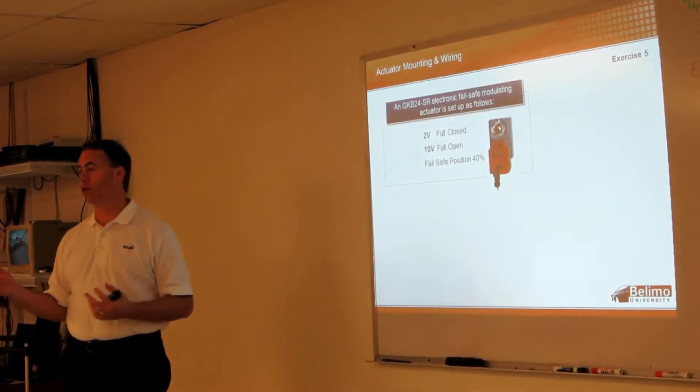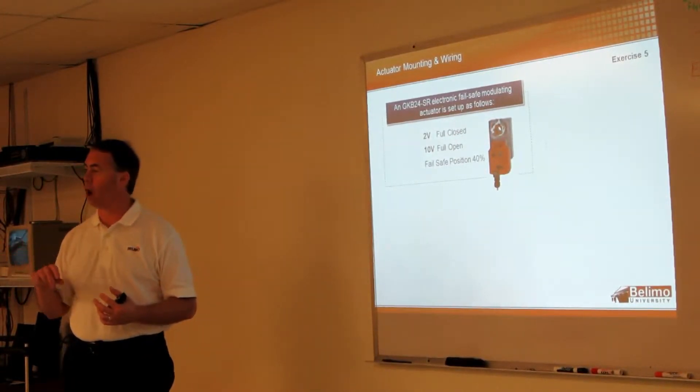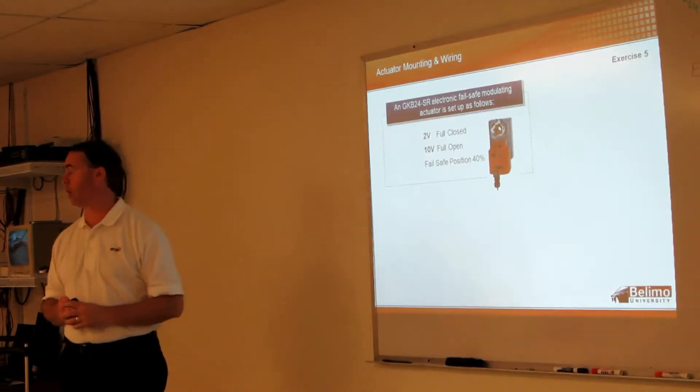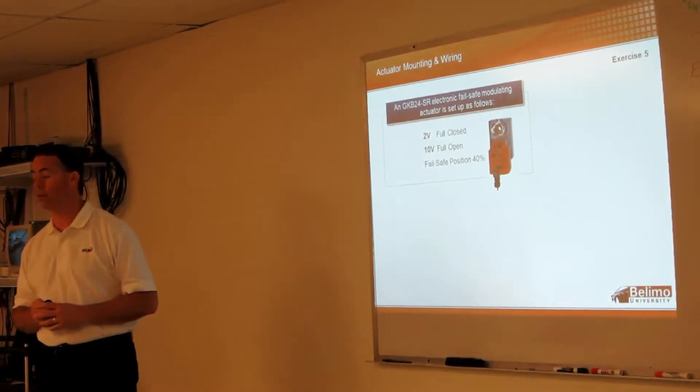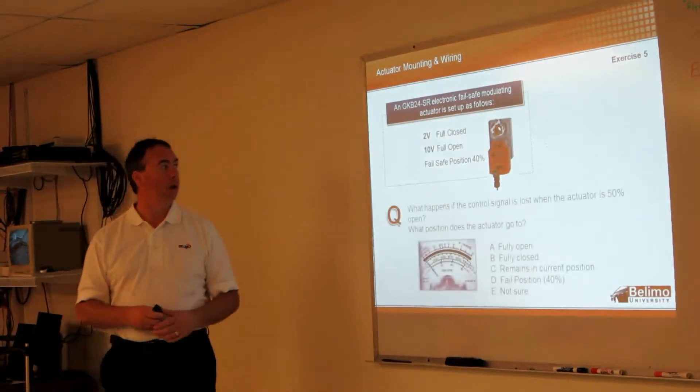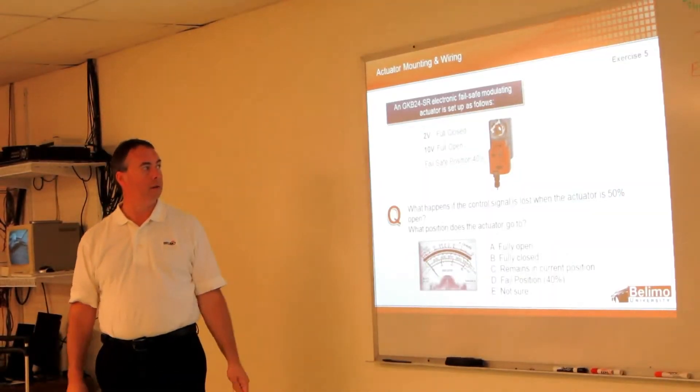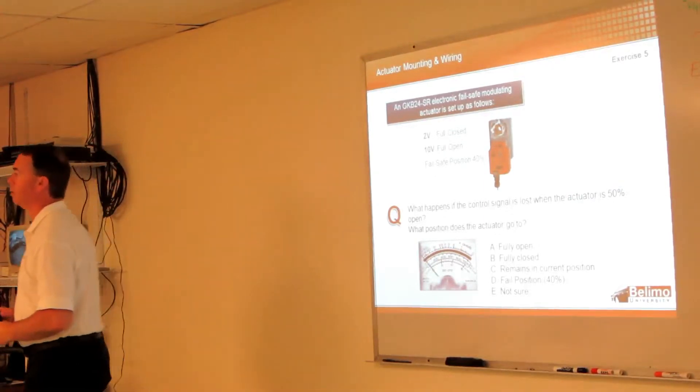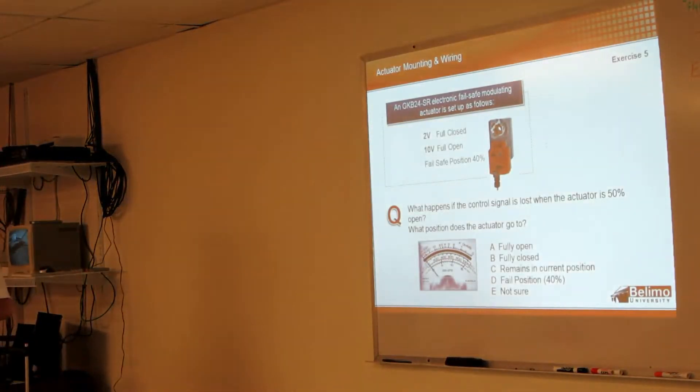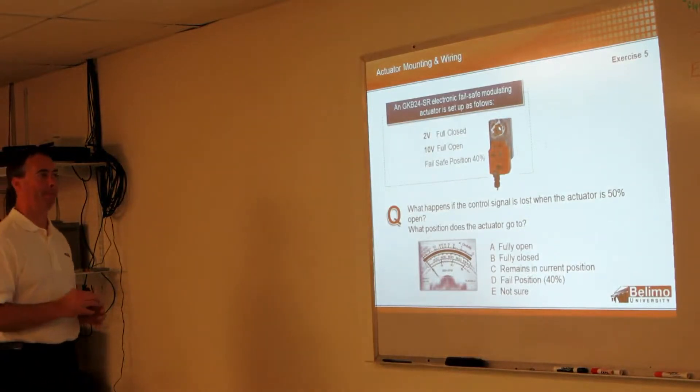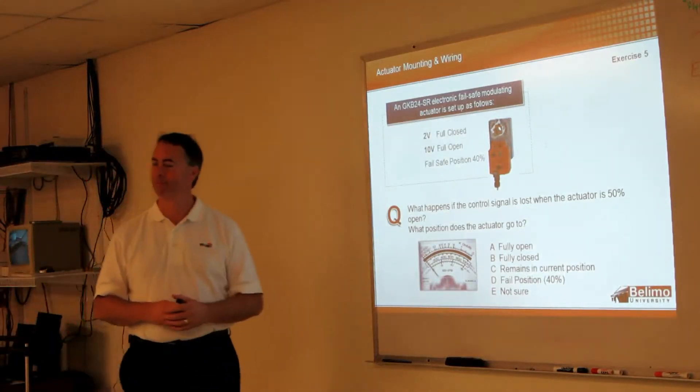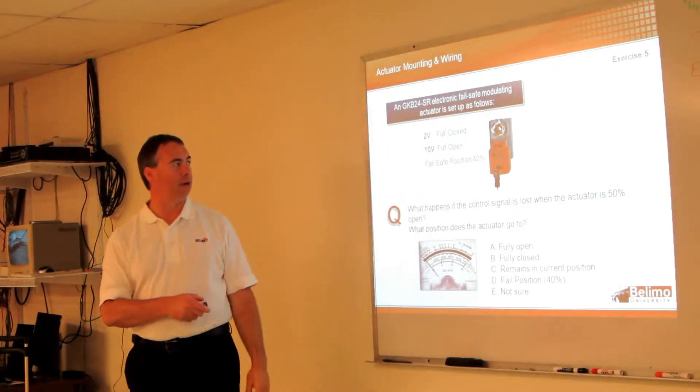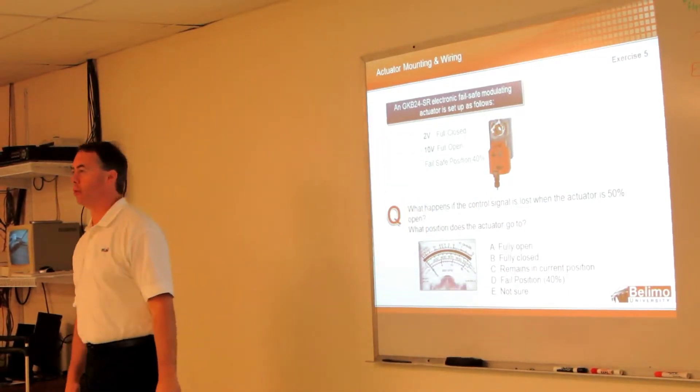You know, spring return, you could do something similar by putting in a hard end stop, but it's nice just through the electronics and electronic fail-safe. So, with this setup here, what's going to happen when we lose control signal when the actuator is at 50%? Oh, close. Yep. Just like the spring return, non-spring, we're losing control signal, it's going to go to its closed position.